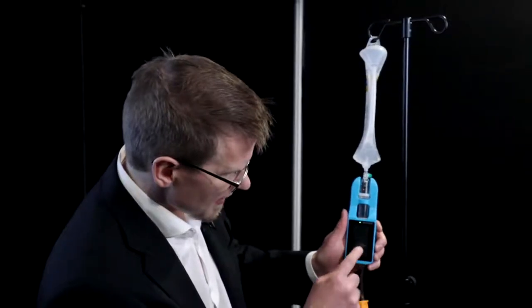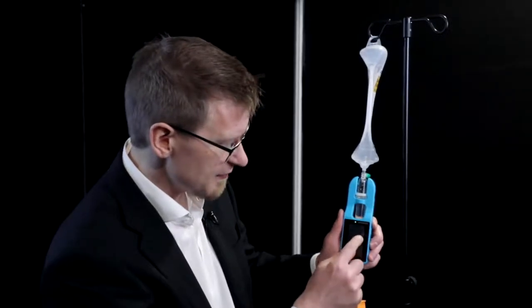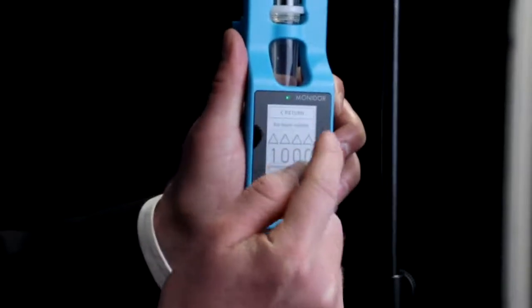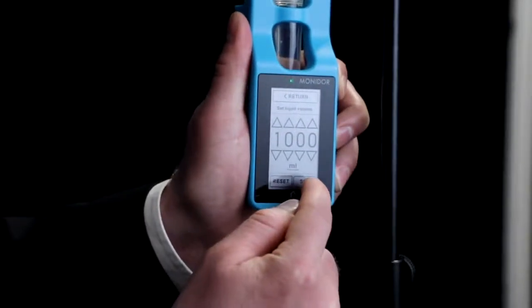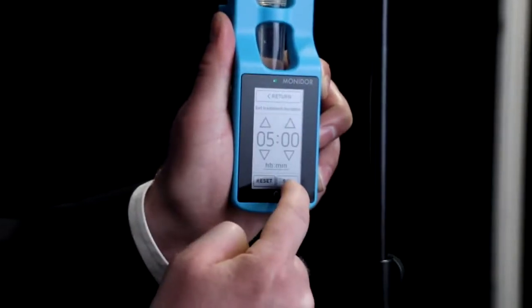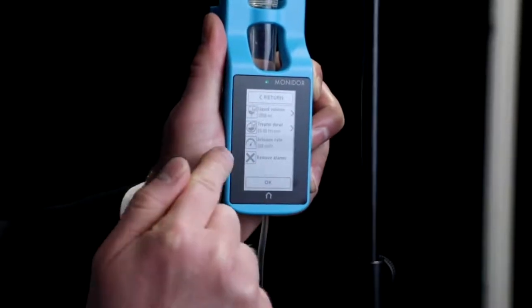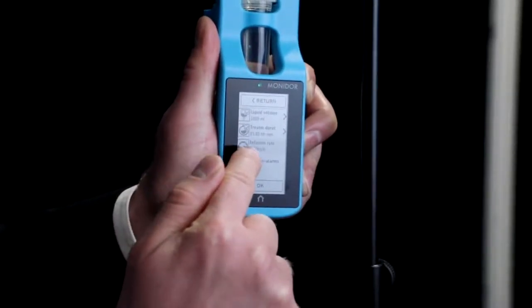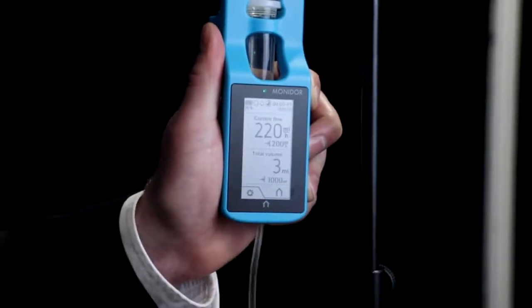It is possible to set alarm limits. There are settings and alarm limits for total volume, duration, and also infusion speed. If you set two settings, it will calculate the third one automatically. If I set an alarm limit for 1000 milliliters and 5 hours, it will automatically calculate the infusion rate that should be 200 mils per hour.